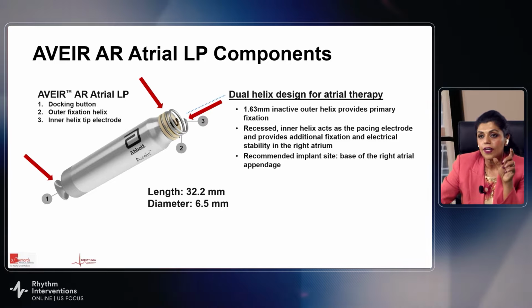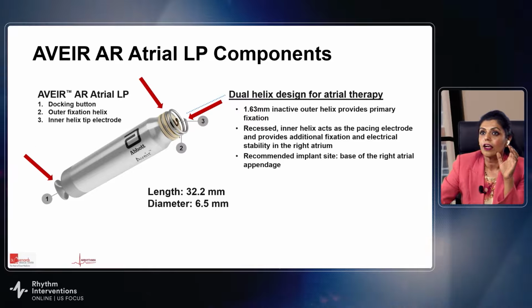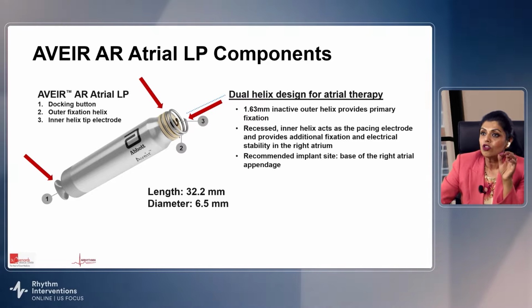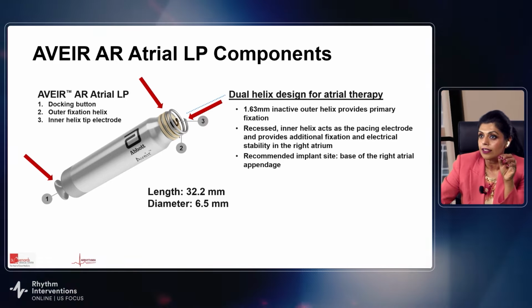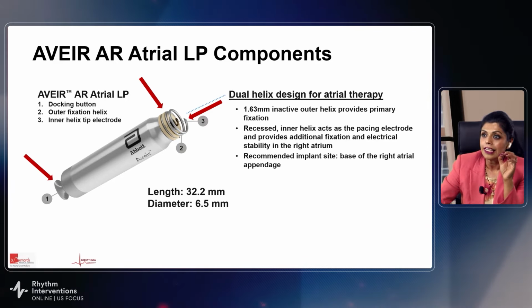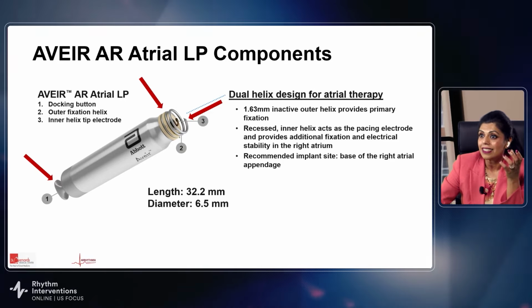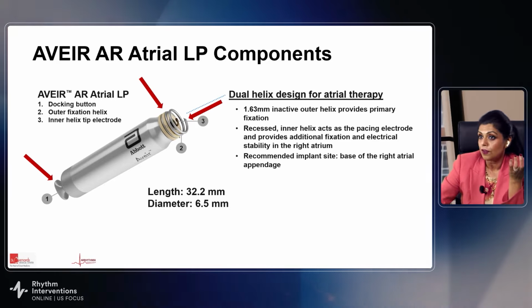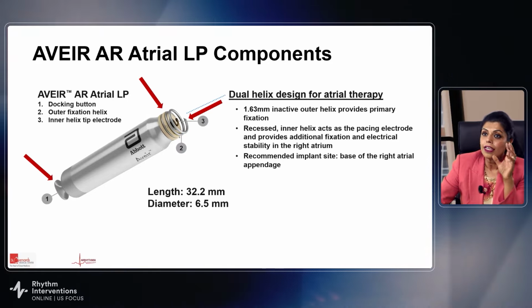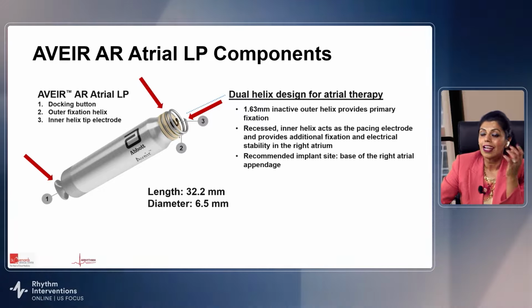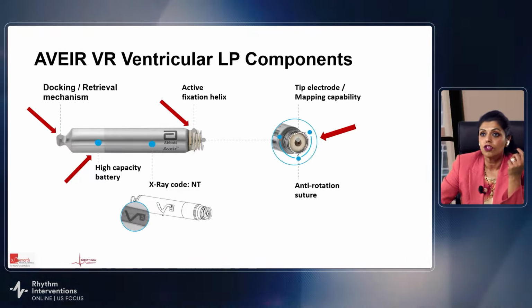Now, the atrial device and the ventricular device look the same, but they have some subtle differences. Both of these are helix fixation devices, but the atrial device does have a dual helix design. So there's an inner helix that acts as a pacing electrode and provides additional fixation and additional electrical stability. It is shorter than the ventricular device. It's about 32 millimeters, but both of them have a docking button that allows for fixation as well as retrievability.